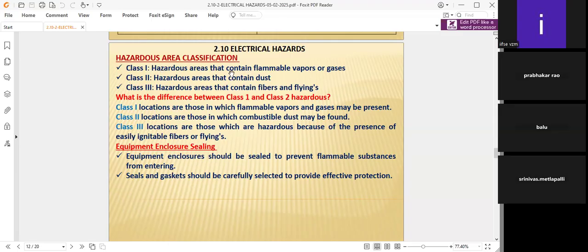Class 1 hazardous area contains flammable vapors or gases. Where the flammable vapors are there, that means the vapors coming from the system will definitely burn at low temperature. That is called flammable vapors or gases. Where the gases have firing capabilities, where ignition is taken care of, even if the source is not there but the vapor is such that it will burn at low temperature or give fire to the surroundings, that is the hazardous area we call it.